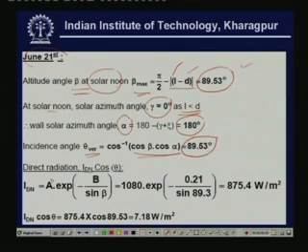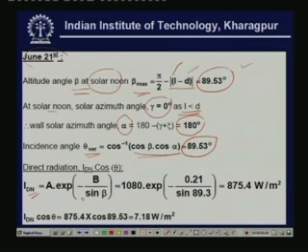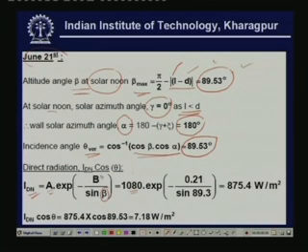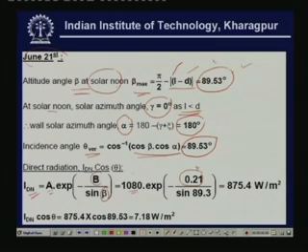Once we know the incidence angle, we calculate the direct radiation on the surface: I_direct = I_DN × cos(theta). From the ASHRAE model, I_DN = A × exp(-B / sin(beta)), where beta is 89.53 degrees, A = 1080 for summer, and B = 0.21 (extinction coefficient) for summer. Substituting these values, the direct normal radiation I_DN works out to be 875.4 W/m².